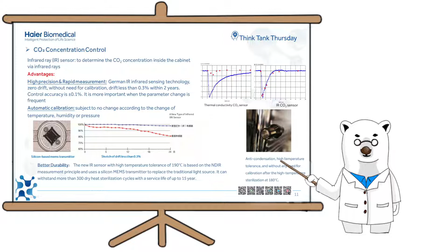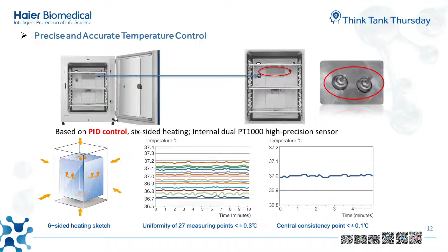Regarding temperature control, the uniformity performance is plus minus 0.3 Celsius degrees and the temperature fluctuation within plus minus 0.1 Celsius degrees is delivered by comprehensive management based on PID control, 6-sided heating and the 2 internal PT1000 sensors. And we can see the environment at different points within the chamber is quite stable, which proves the stability and reliability for research.